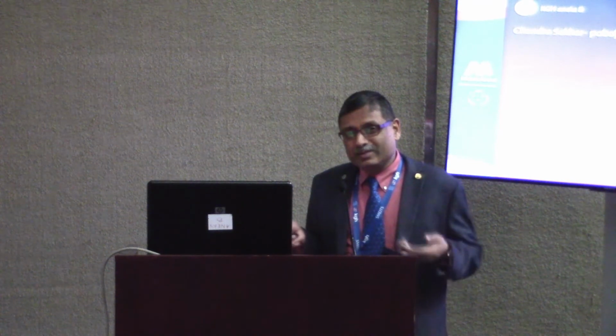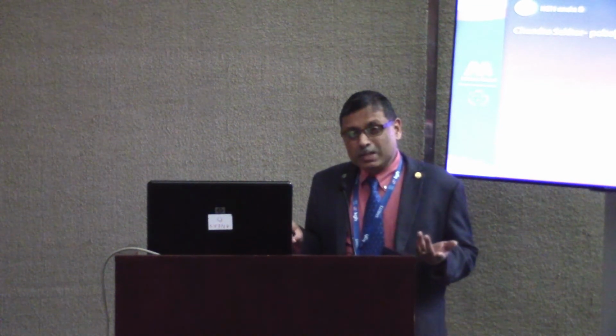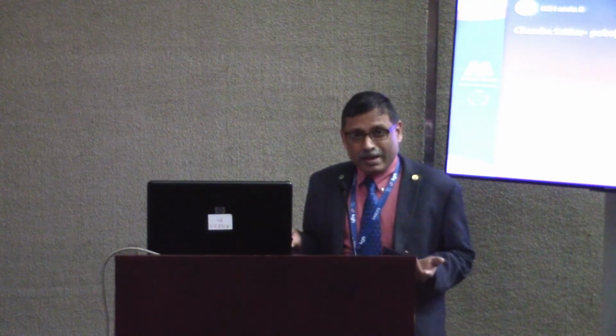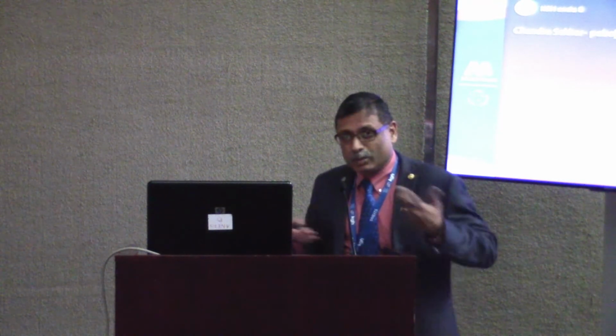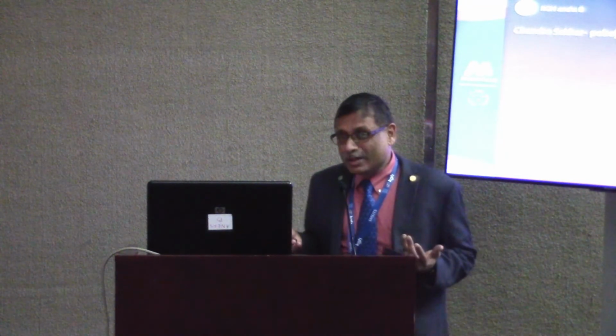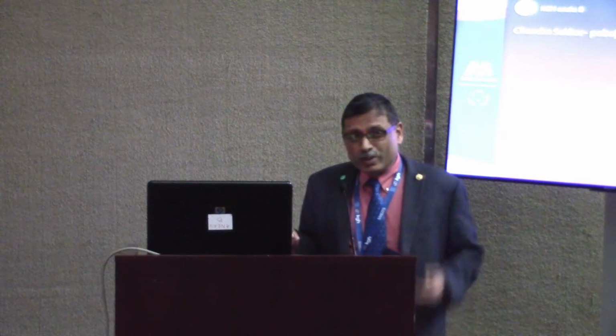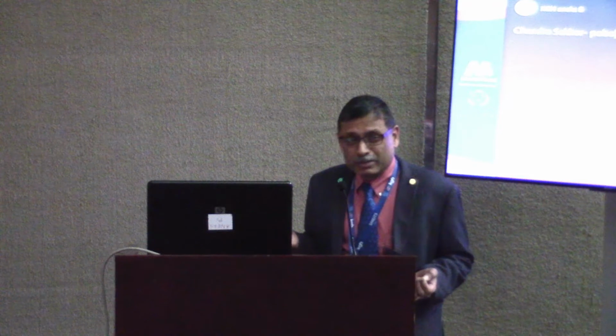Here it is: high temperature cooling and dehumidification. We're beginning to see that humidity level inside a building above a certain value, say 80% relative humidity, has a tremendous impact on how we perceive comfort. But anything around 60 to 65% relative humidity gives better means of providing comfort. So the question is, do you really need to dehumidify down to a very low dew point temperature? It turns out we may not need to do that all the time.